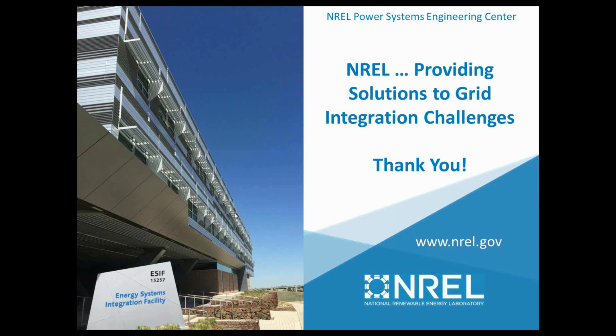Hawaii is having a trickier time in that their grid is a little less stable in terms of fixed voltage and frequency than the mainland grid. So they already open up voltage and frequency set points just to stay online on that system. And now, dealing with the unintentional islanding requirement has basically gone to the back burner when they're focused on just making sure all the DGs can stay online and support the grid in that particular scenario. So we're seeing this be an issue with practically anybody and everybody that is installing PV, and that happens to be practically every utility in the United States.